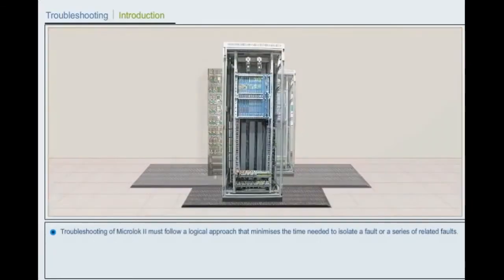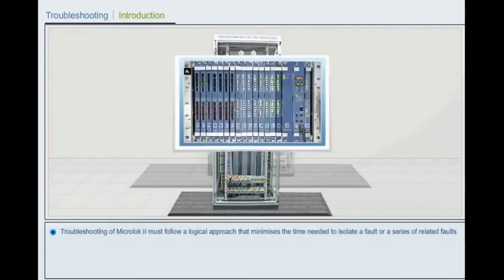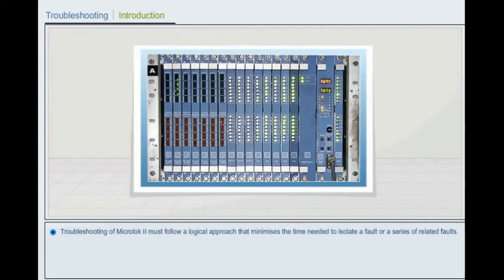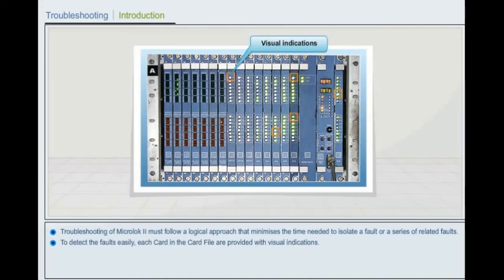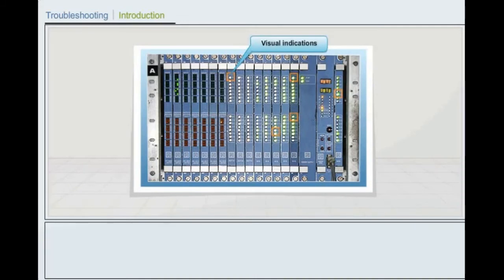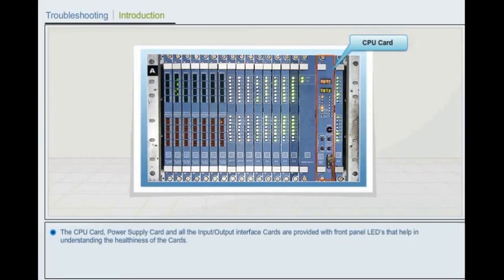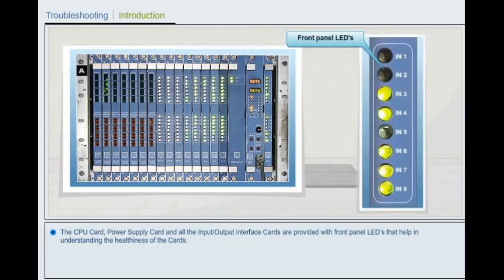Troubleshooting. Introduction. Troubleshooting of Microlok 2 must follow a logical approach that minimizes the time needed to isolate a fault or a series of related faults. To detect the faults easily, each card in the card file is provided with visual indications. The central processing unit card, power supply card, and all the input-output interface cards are provided with front panel light emitting diodes, LEDs, that help in understanding the healthiness of the cards.